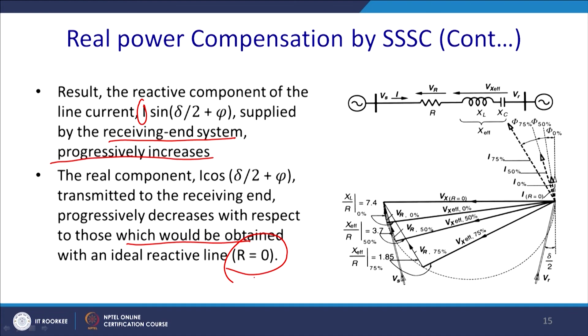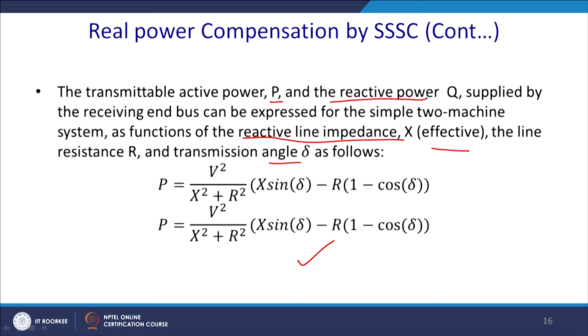The transmittable real power P and the reactive power Q supplied by the receiving end bus can be expressed for the simple two machine system as a function of the effective line impedance. So, we have to incorporate now the value of the line resistance R and the transmission line angle delta as follows: V square by (X square plus R square) into (X sin delta minus R(1 minus cos delta)). Effectively you can couple it. So, this will be the new equation for transmitting power with reactive power compensation, and thus what happens? You can see that the line changes.